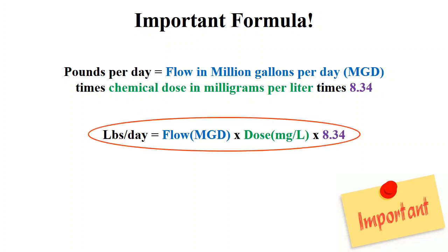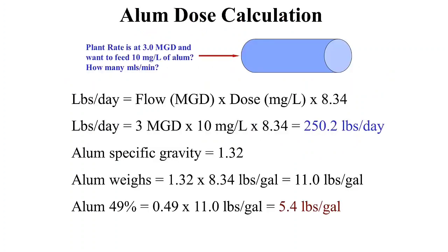This formula is very important and should be memorized by water treatment plant operators. If you're working at a plant and the computer system is down, you have to manually set the alum feed pump to feed 10 milligrams per liter of alum at a plant operating at 3 million gallons per day. How do you know how many milliliters per minute you need to feed?